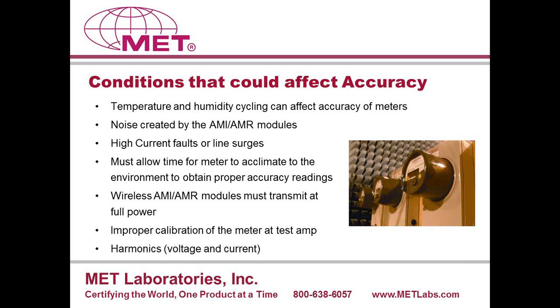Harmonics, both voltage and current, could affect accuracy as well. I'll note that at this point, at this stage anyway, the ANSI standard does not include any harmonics testing, but it looks like that's on the way. We are on the ANSI committee, and we attend the ANSI meetings for the electricity metering, and it looks like at some point in the future there will be harmonics tests included in the standard, along with some other issues. And again, it's really prompted by seeing problems in the field, and utilities are involved and manufacturers are involved, and they see these problems and they get written into the standards to help clear those types of issues out before products hit the market.